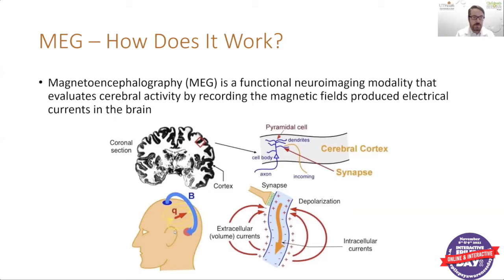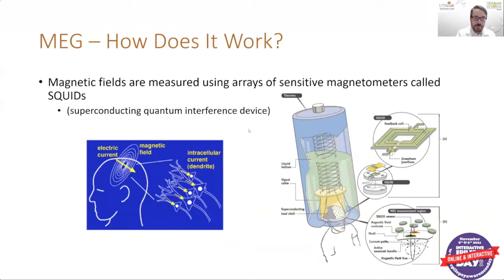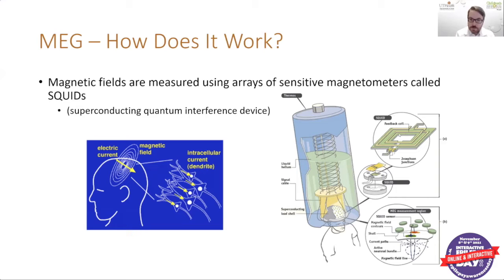How exactly does it do that? MEG uses what we call SQUIDs — superconducting quantum interference devices. These magnetic fields are measured using an array of sensitive magnetometers. You can see this coil which basically detects that magnetic field, and that is included within the SQUID sensors. Here you can see the direction of the electrical activity, the magnetic field circling around it being detected by the SQUIDs, and the representation of the patient within the scanner.